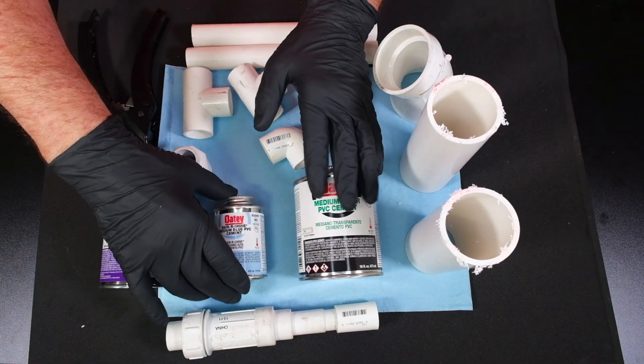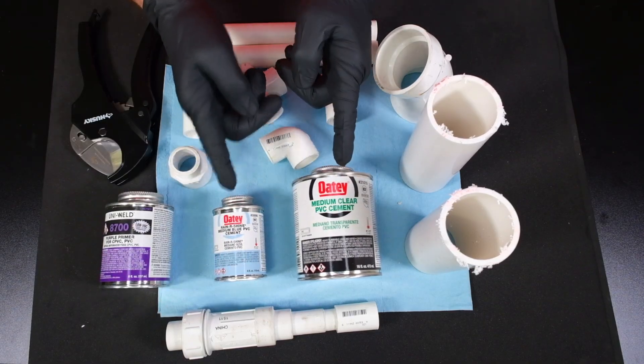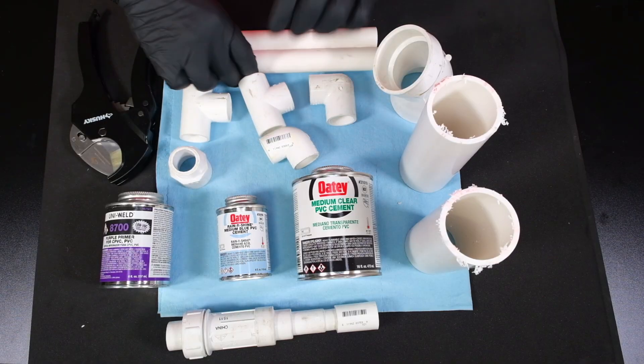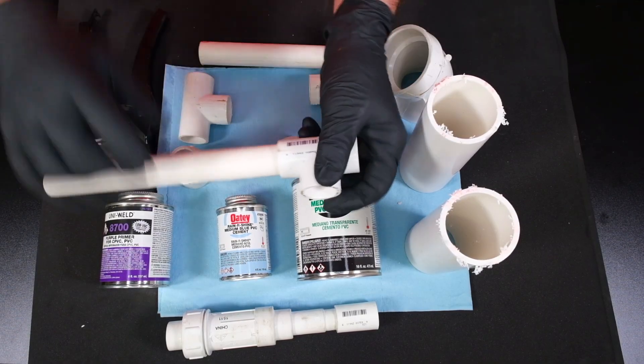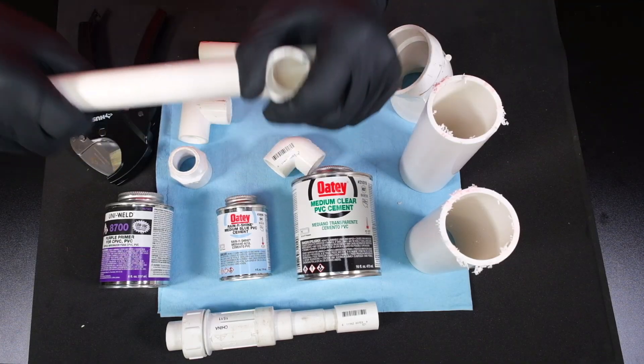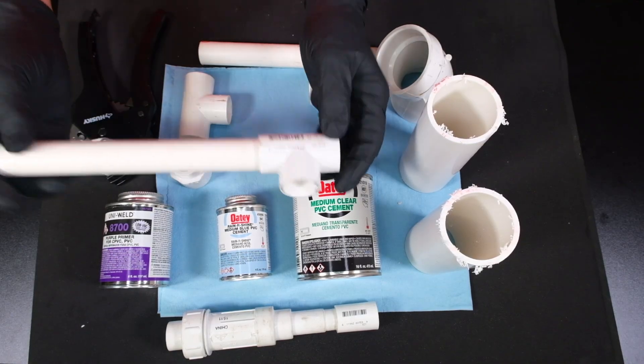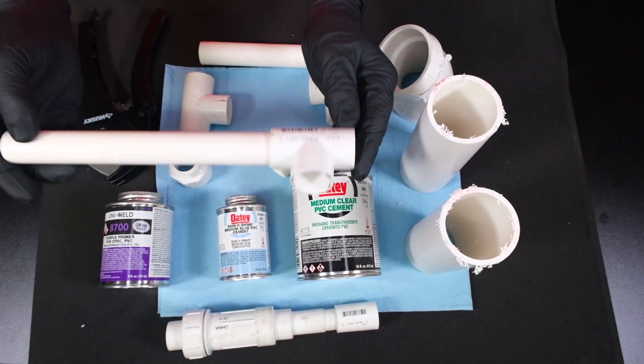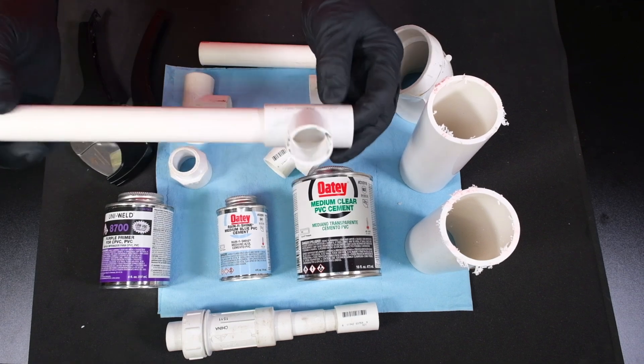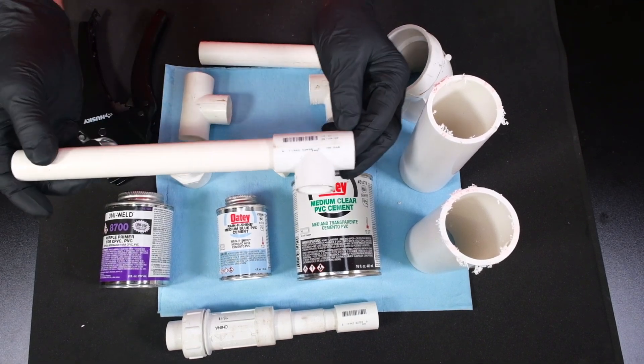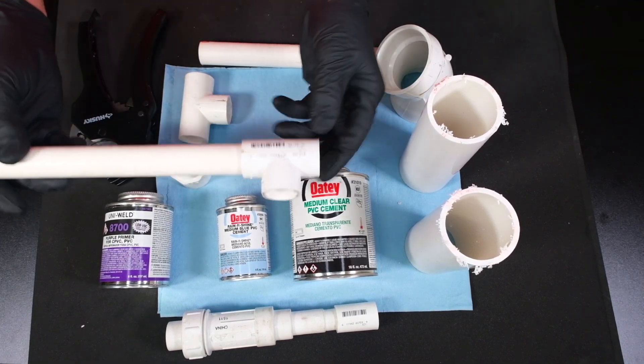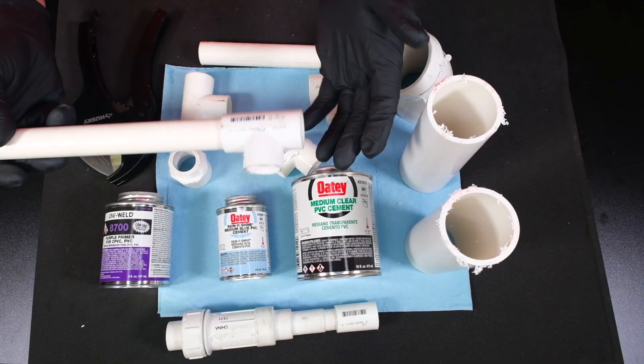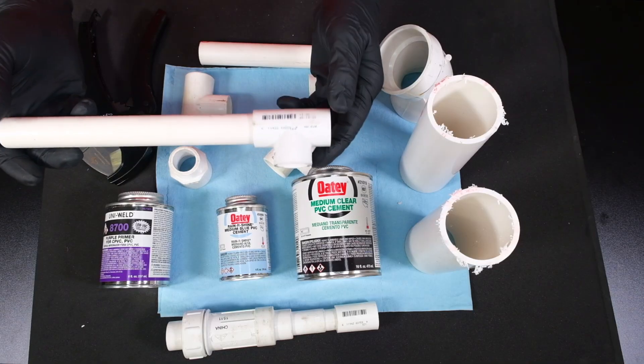My experience has been most PVC solvent weld cements take a minimum of several hours to set up and cure for standard water pressure. Now this glue and this glue say the exact same things on the back. They say hold together for 30 seconds. In 15 minutes, it's ready for handling. And it's not ready for pressure for at least two hours if it's above 60 degrees. If it's lower than 60 degrees, it's going to take longer. If it's 110 degrees outside, it's going to set up faster.